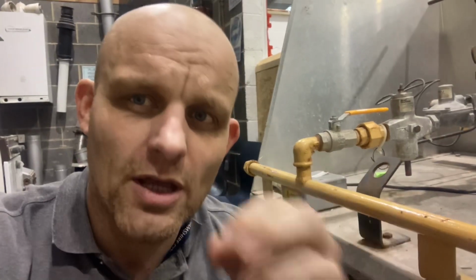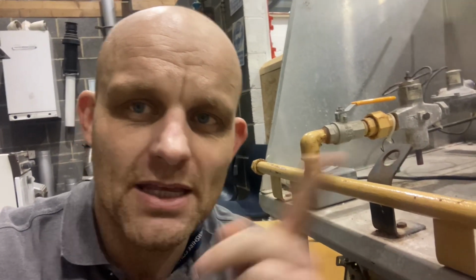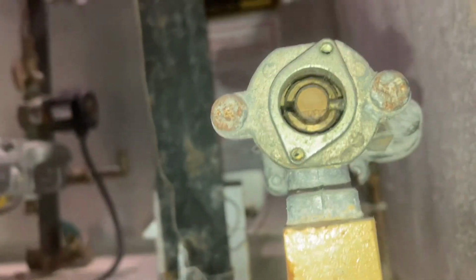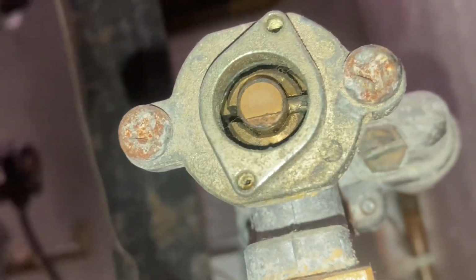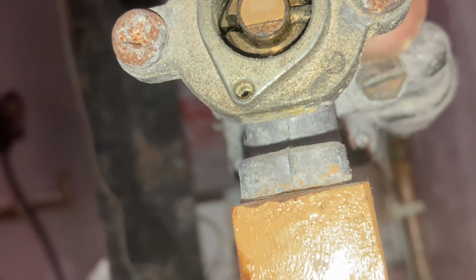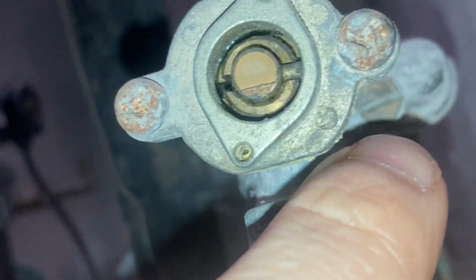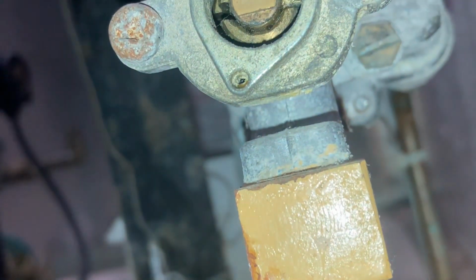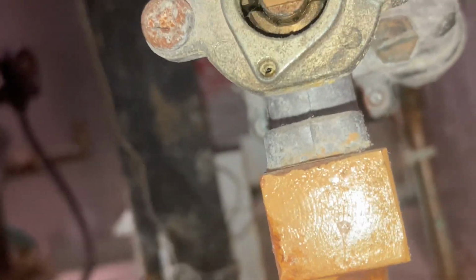So the job of the bypass is so that when the flame is modulating, fluctuating, it can always reignite itself, because the bypass keeps the gas supply flowing and constantly ignited. So the bypass is a little screw that allows gas to constantly flow through the gas tap. And here's a picture of one, or a video of one. Just there, look. Undo that screw and you'll see a little nozzle.